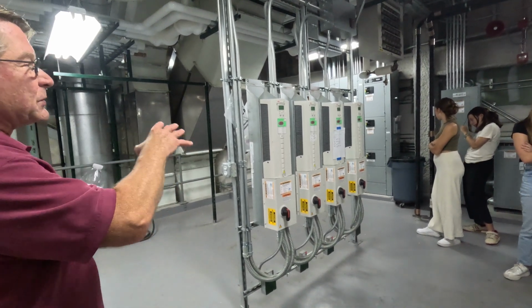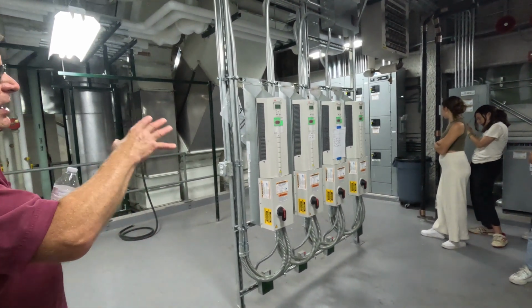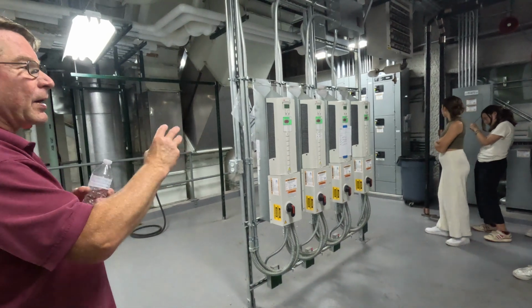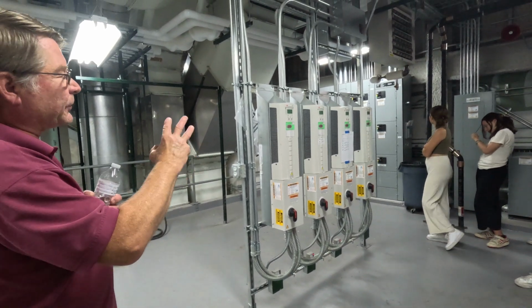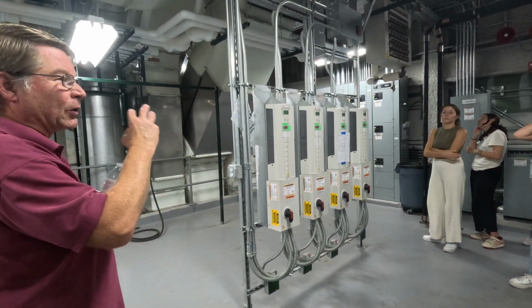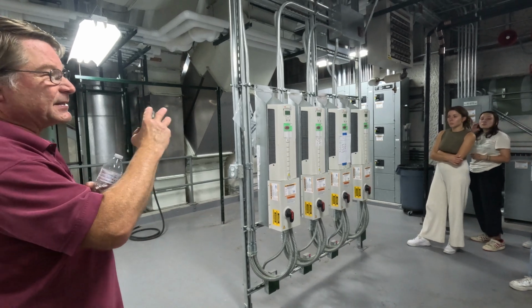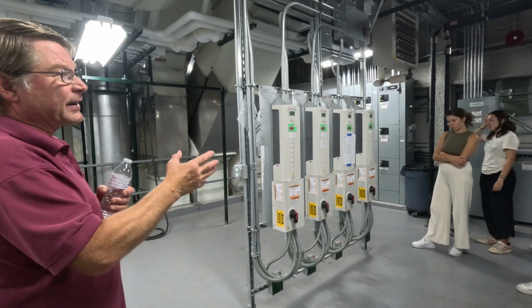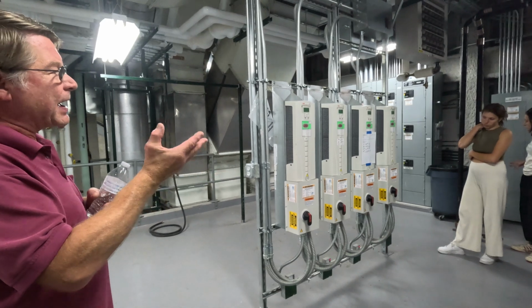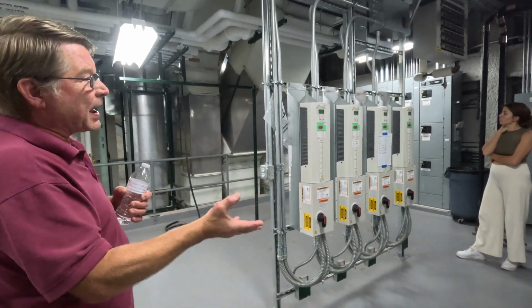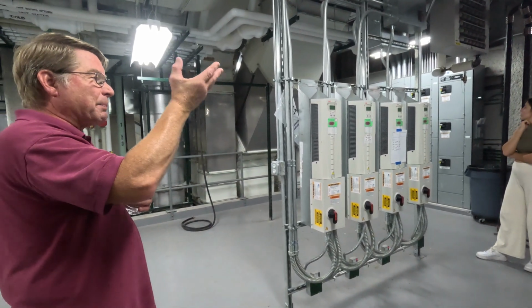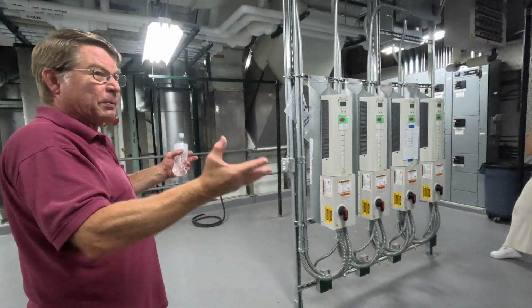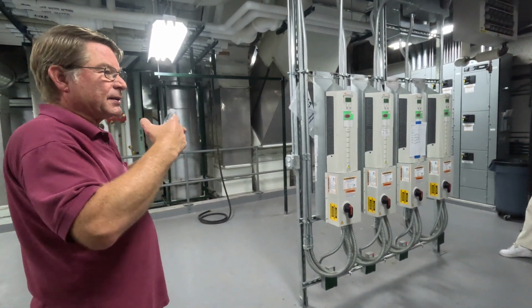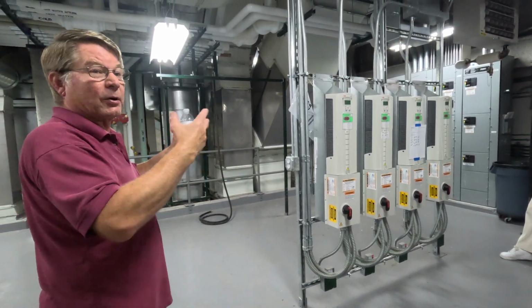The exhaust fans have to work on a different system. The exhaust fans, there's always 3 that are running, 1 that's in standby. The 3 that are running have to run at full speed. They run at about 56 hertz, and the reason for that is that these fans have to have enough velocity in the air to get it 100 feet in the air past the end of the stack before dispersion, and that way you don't get any kind of fumes going over into the neighborhoods over there.